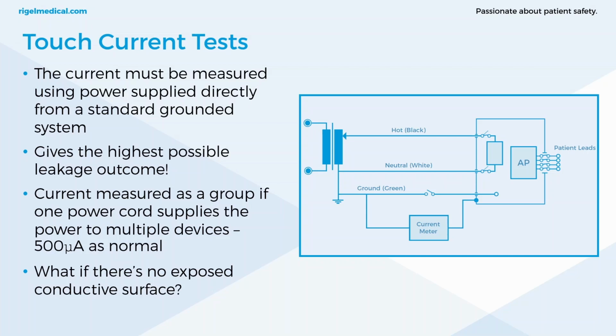This is where you could also use the recommendation of a grounded service, which is if you've got a non-TN system and you need to test that device in situ wherever you are, then you can briefly ground one side of the isolated power system for the leakage measurement.